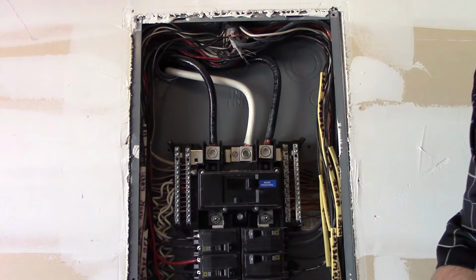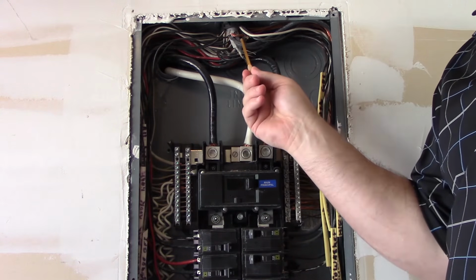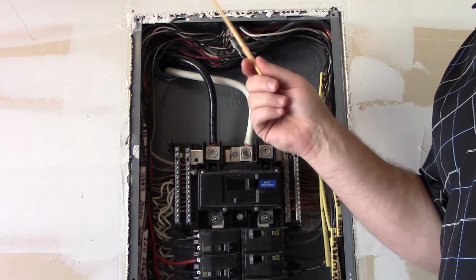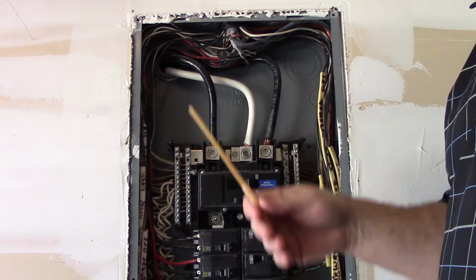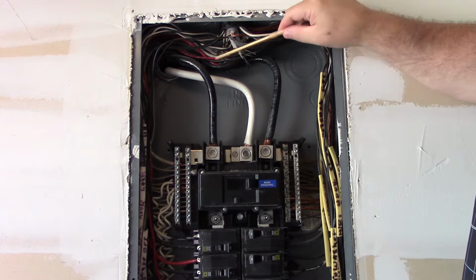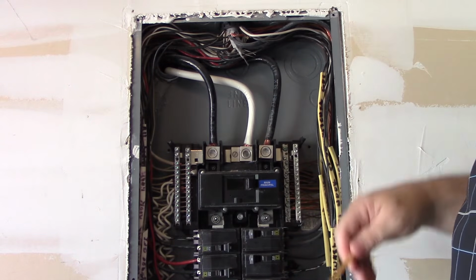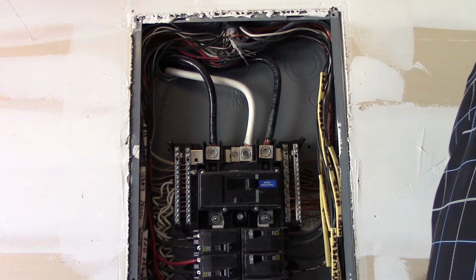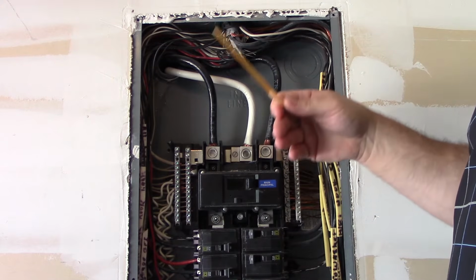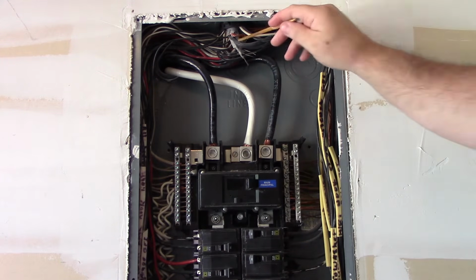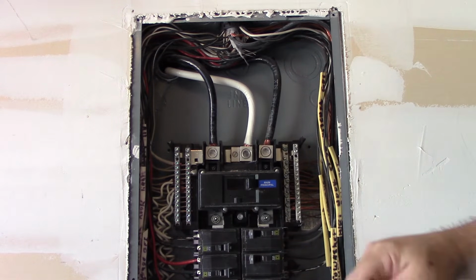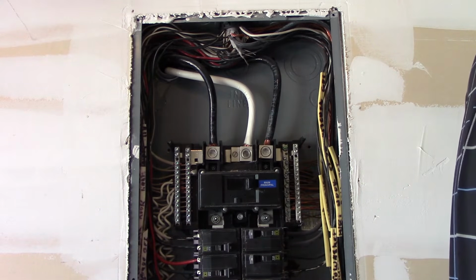But again, as an inspector, municipal violation. Home inspector, call it out because you don't want somebody later to have a problem in this wall because of this issue right here and somebody tell you you missed it. So you want to call it out, but you're not going to flame it. You're going to let the electrician determine whether or not it's okay and let them be on the hook for that. Defer their liability to them.